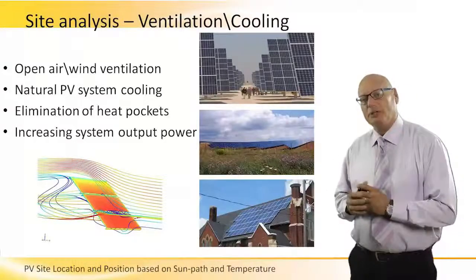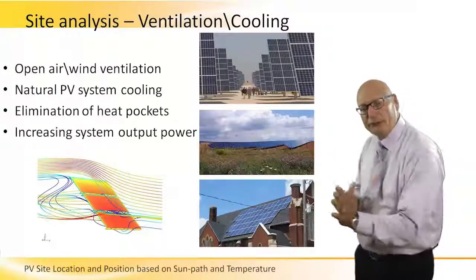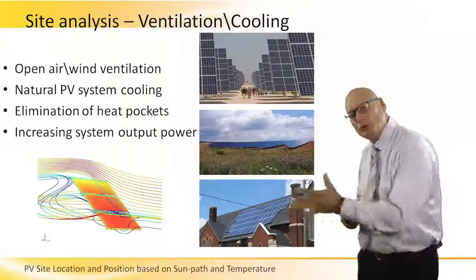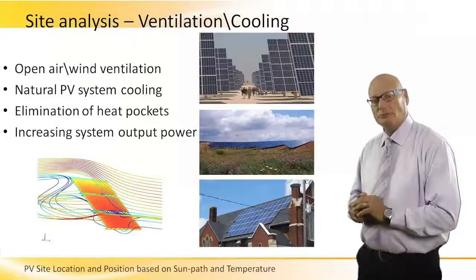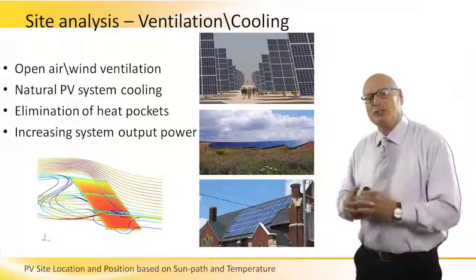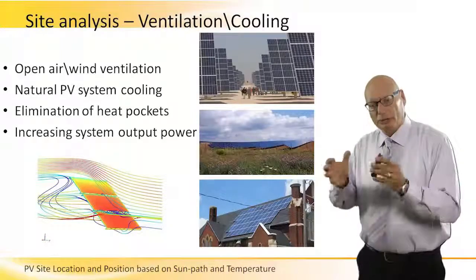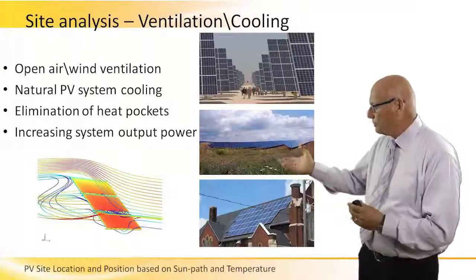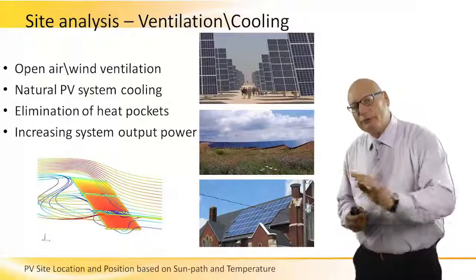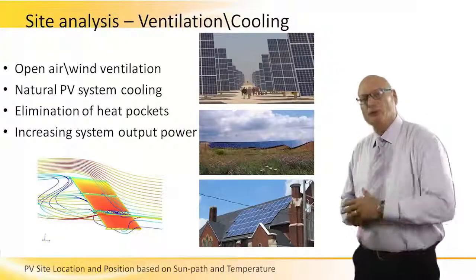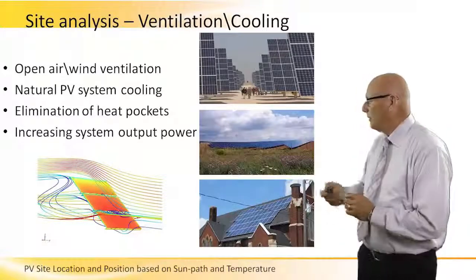We just said ventilation and cooling. Look at the picture on the left — it's a representation of wind flows along, across, and through the panel. We would like as much air moving through the panel as possible in order to cool it down. It's a natural PV system cooling. We want to eliminate the heat pocket. When we do that, we increase the output power. Look at the picture on the bottom right — it's an array just a few centimeters away from the roof itself. Heat pocket. No air can flow through. No cooling. Less efficiency.